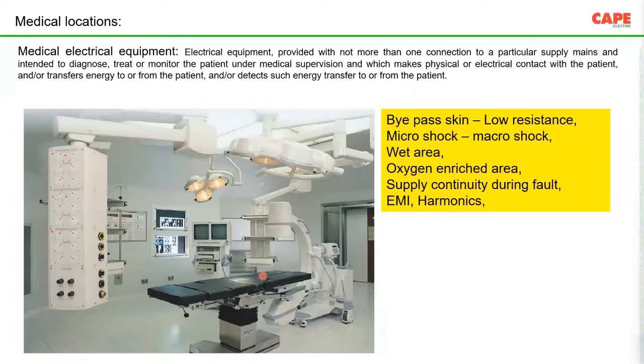Then in some of the areas in hospitals, it is oxygen enriched area, means the amount of oxygen, because say for example, an operation theater, oxygen is used. As a result, the oxygen content in the area is very high. I'm sure most of all of you are aware about the fire triangle. You need fuel, heat, and something to burn, oxygen. If oxygen is more, the chance of fire is more. Then one of the requirement is supply continuity during fault, which I will explain later. Plus the other requirements are EMI, harmonics, and so on. So basically, medical locations are special areas where we really need to treat people, or really need to treat the electrical appliance very specially. We cannot apply the normal rules and regulations in a medical location.